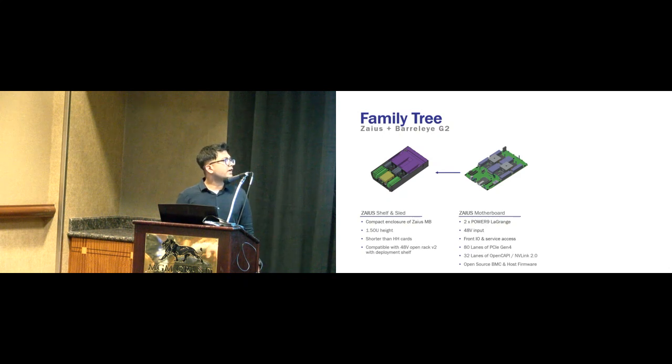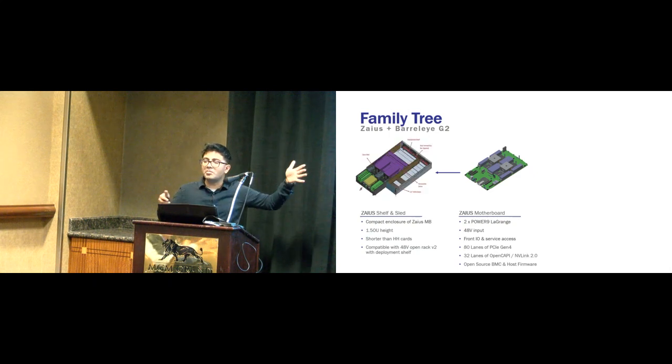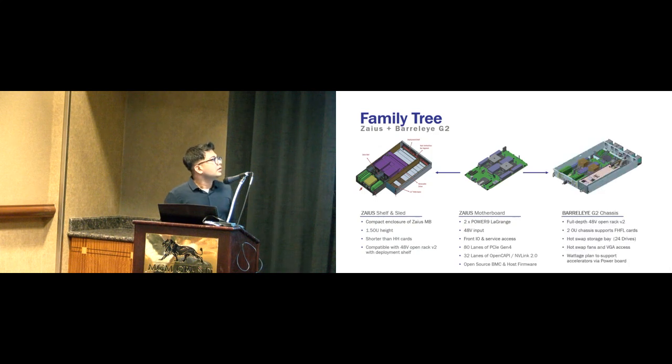And it's a 1.5 OU tall server. It's essentially a compact enclosure of the motherboard, right? It's shorter, so it can fit half-height, half-length cards. It's compatible with 48 volts Open Rack, but you do need a deployment shelf that goes around it to make it wide enough, essentially 13 inches to 21, and to increase the depth to fit it in the Open Rack.